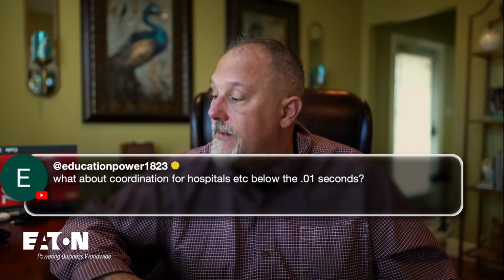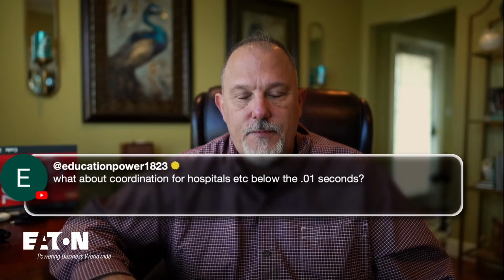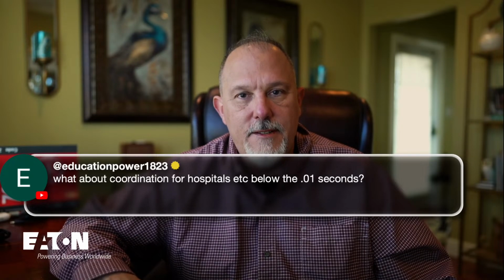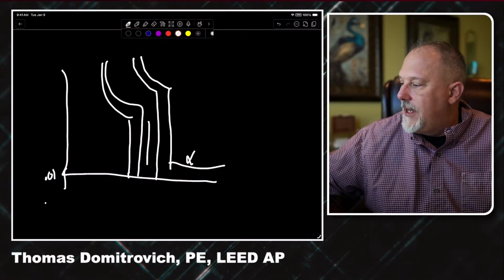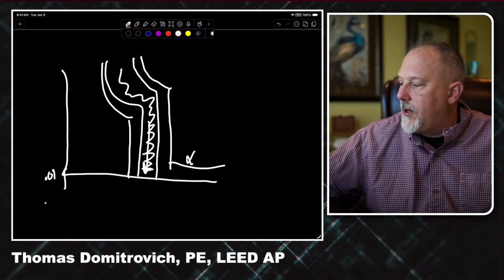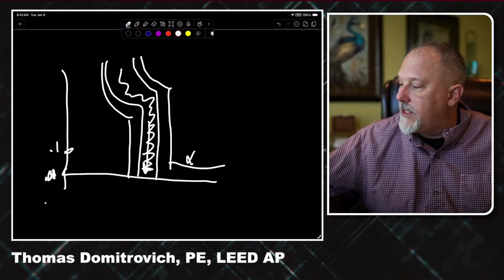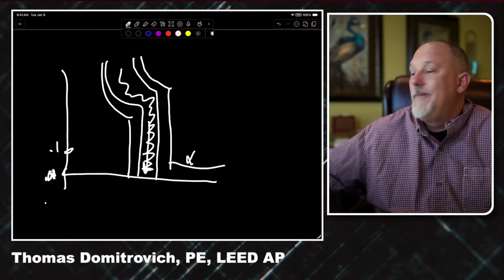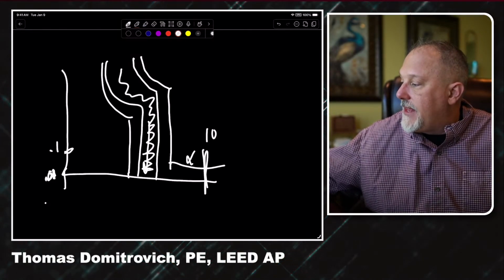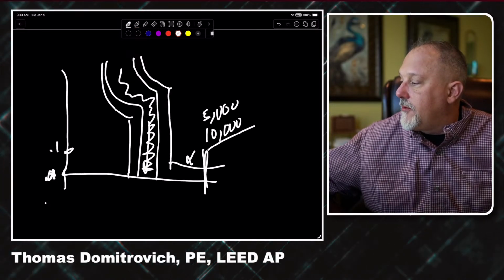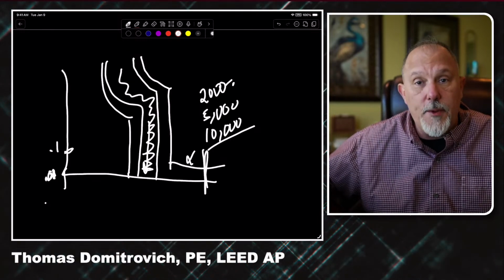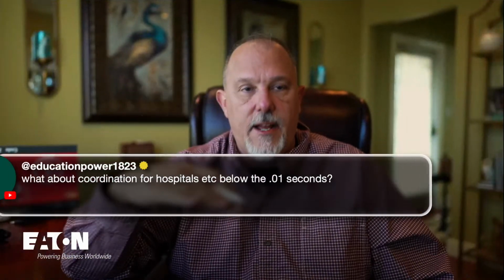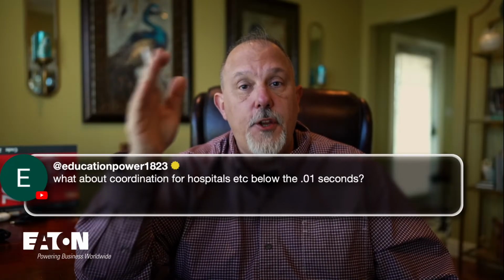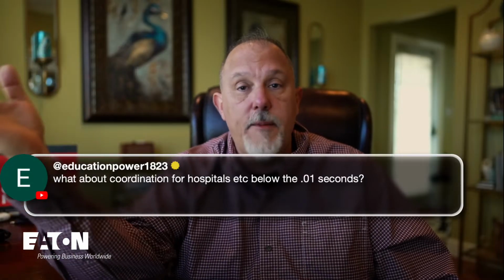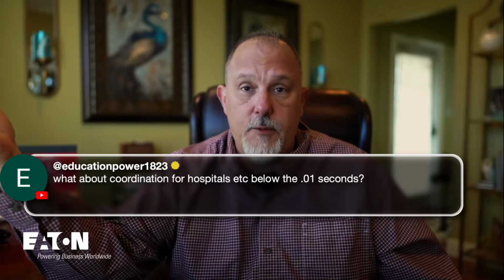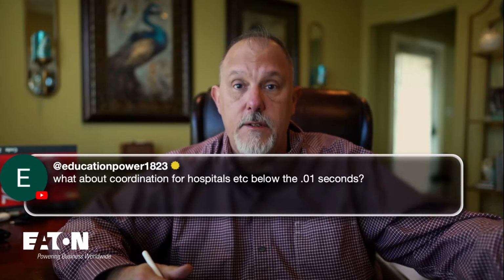I've heard that before. You can't do that, because you need to consider current. If I looked at these two curves, I have complete separation all the way down to 0.01 seconds. And I've heard people say, forget about 0.1 seconds, we want to coordinate to 0.01 seconds. Well, these coordinate to 0.01 seconds. I've got complete separation. But yet, if I've got 10,000 amps flowing through them, 5,000 amps, or 2,000 amps, they're both going to open. So I can't just say time. I have to include current. What value of current do you want to coordinate to? If it's not the three-phase bolted fault, do you pick the most common fault in a power system, which is the ground fault? I'm good with that. If you're good with that, I'm good with that. I could stand on the witness stand and defend that action, I think.